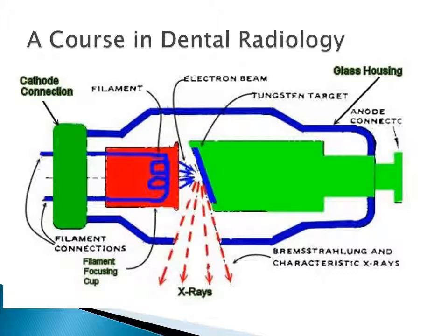So then I'm going to apply my kVp, where you see this dotted line going across. I'm going to apply my kVp across there, which will generate that difference in potential to cause those electrons that are being pulled up here to come shooting out, hit my anode, and when they hit my anode, that's where we're going to generate our X-rays.